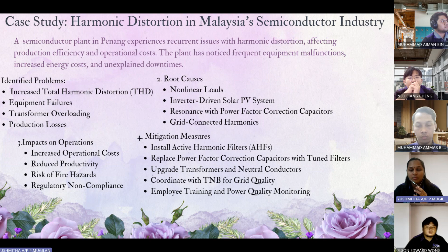The root causes are non-linear loads, an inverter-driven solar PV system, resonance with power factor correction capacitors, and grid-connected harmonics. The impacts are increased operational cost, reduced productivity, risk of fire hazards, and regulatory non-compliance. The mitigation measures are to install active harmonic filters, replace power factor correction capacitors with tuned filters, upgrade transformer and neutral conductors, coordinate with TNB for grid quality, and provide training for power quality monitoring. Next, I will pass it to another group member.